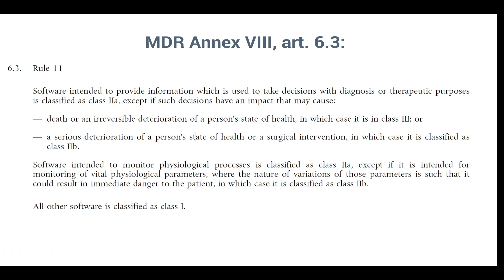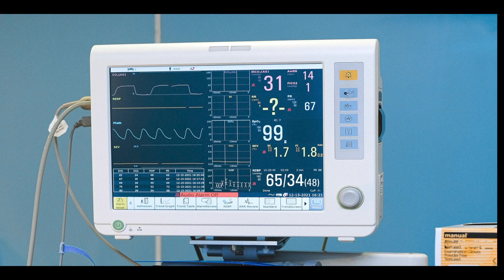If the software is used to take diagnostic or therapeutic decisions, it will be Class 2A, unless such decisions, when made wrong, could cause death or irreversible negative consequences for someone's health. Then it's Class 3. And when the health consequences are serious or could require surgery to get fixed, it's a Class 2B. If the software is intended to only monitor physiological processes, it is Class 2A, or if the monitored process is vital and wrong monitoring could put the patient in immediate danger, the software is Class 2B. All other software is Class 1.